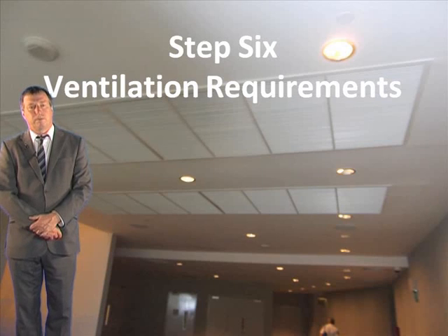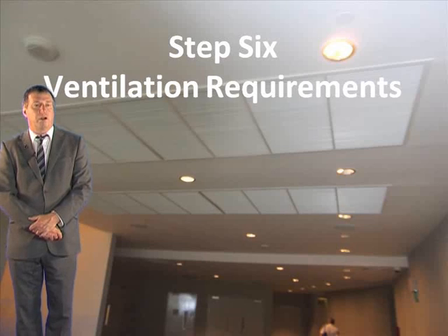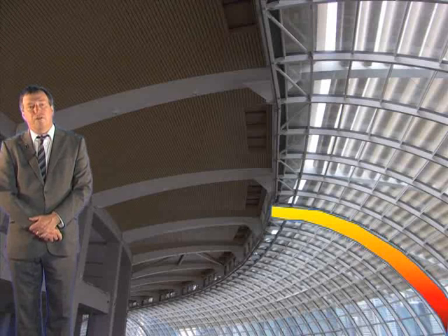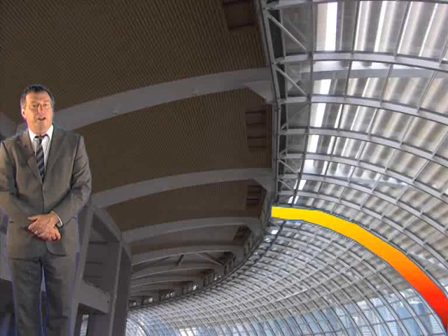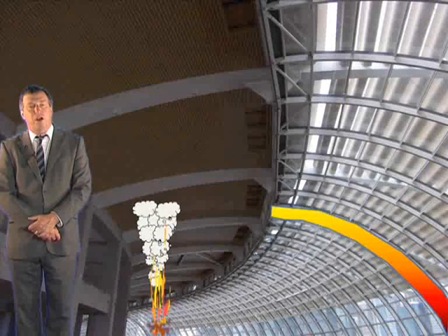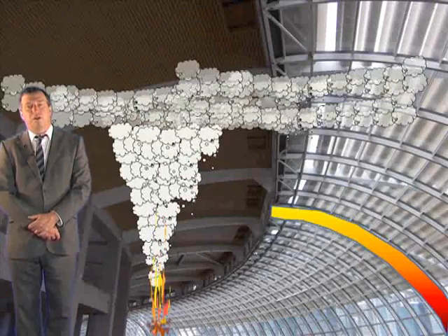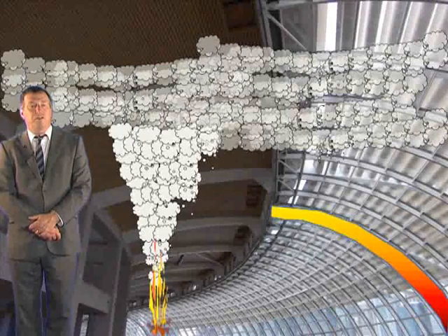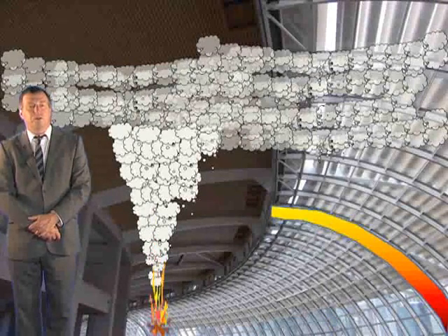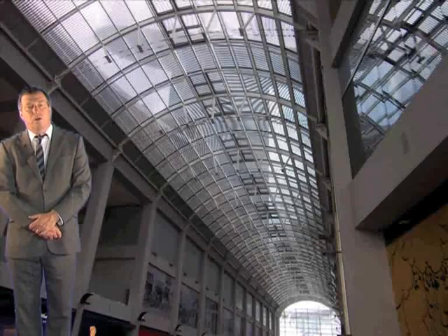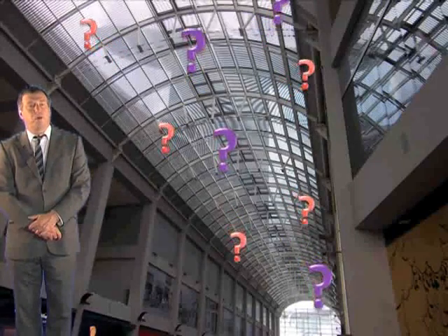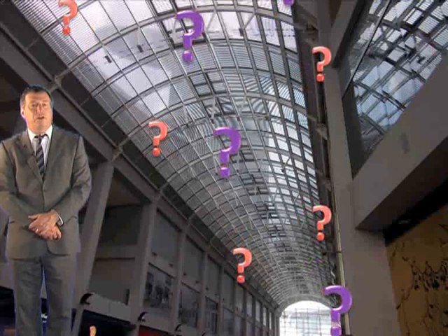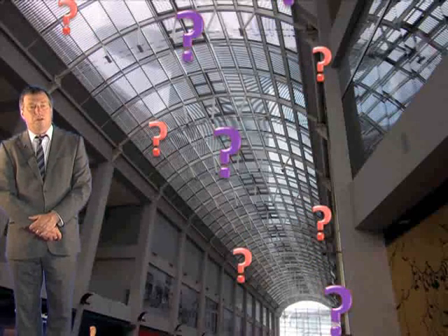We'll look at ventilation requirements, starting with the number of reservoirs that might be required. A large building will normally have a number of separate smoke reservoirs within it, and one objective of any smoke control system is to ensure that smoke from a fire only affects a single reservoir. This is so that damage is limited in extent, people are put to minimal risk, and the smoke exhaust system functions correctly. We'll examine how many reservoirs might be required, but first we'll look at some of the principles behind smoke reservoirs.